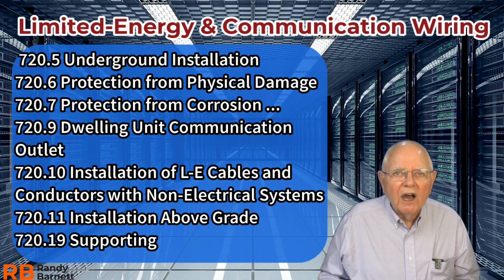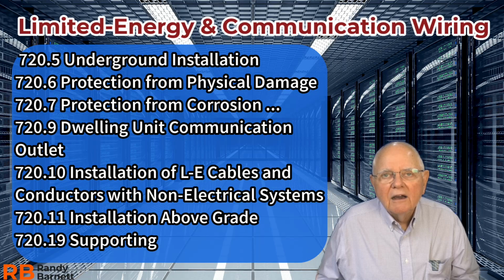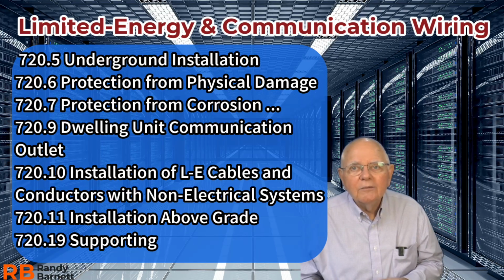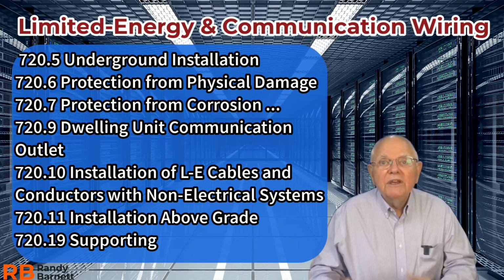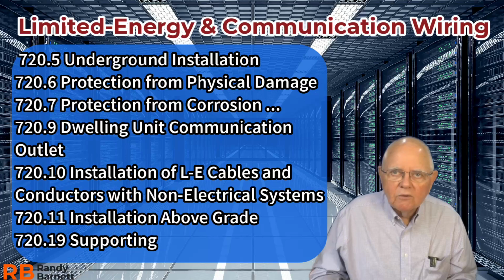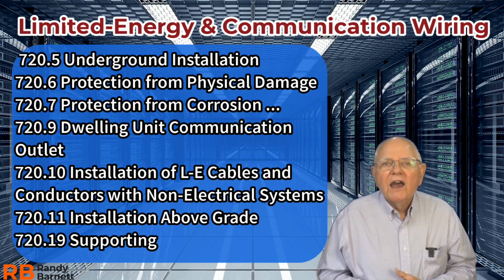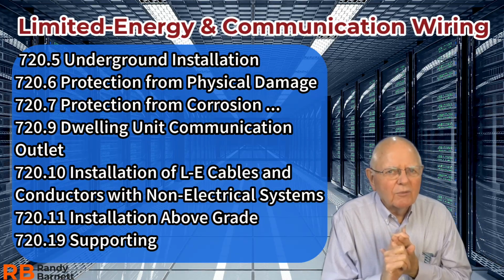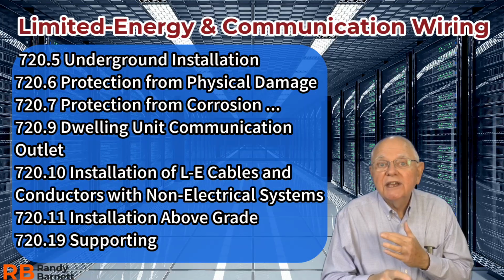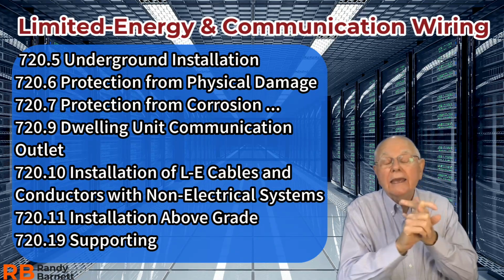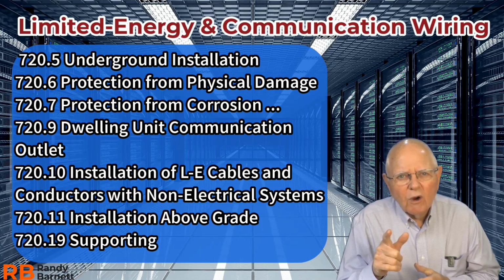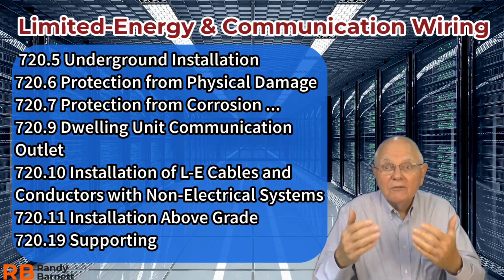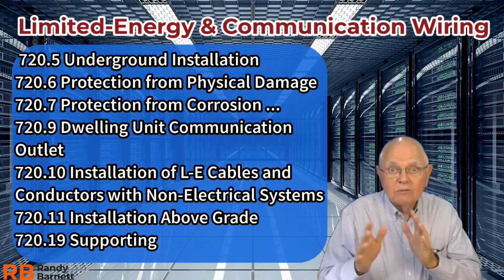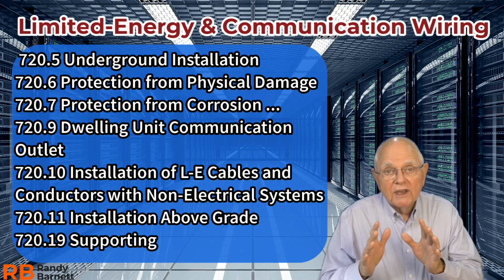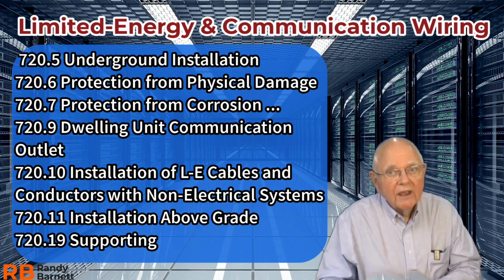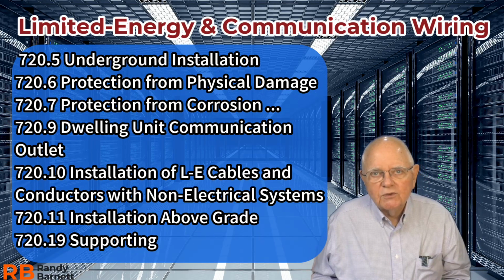Subsection C of 720.5 talks about when I go underneath a building with my limited energy run. The general rule is underground limited energy cables installed under a building have to be in a raceway. Okay, that makes sense, and we normally do that. But there are some exceptions. It says if I run any one of 3 types of cables, I don't have to put them in a raceway: optical fiber, communication cables, and coaxial type CATV cable. Coax, right? Okay. There's a similar requirement now in 720.11 for cables above ground. There's an exception that these cables do not have to be in a raceway above ground in a wet location. But it adds one more cable. It adds network-powered broadband cables as an exception as well above ground.